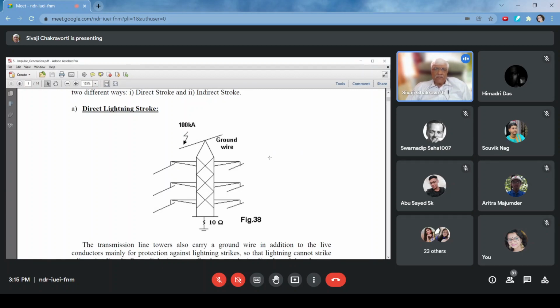Now this traveling wave, particularly the current, when it travels and encounters an impedance which is not of the R plus jX sort, it is called surge impedance. That surge impedance, whatever Z is, multiplied by this current gives the equivalent voltage of that lightning strike. If you ask me what the surge impedance of a transmission tower is, it will be approximately between 300 and 500 ohms. The bigger towers will have something around 500 ohms, the smaller towers around 300 ohms.